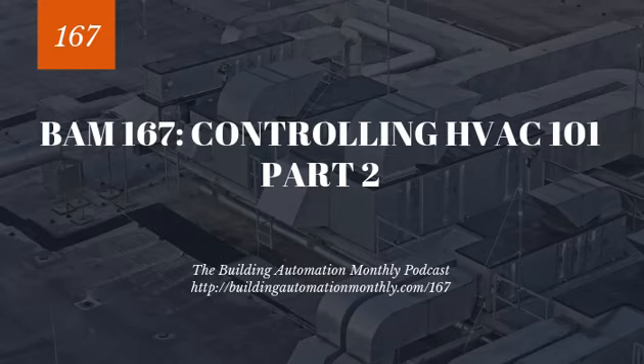Is it going to be manufacturer controls and you're using a BACnet interface, or are you controlling them? Because your ability to sequence systems is going to be dependent on whether you're putting a field controller on, or if you're pulling in BACnet or LON or whatever points from that rooftop unit. So that's the first thing you've got to figure out. Once you know that, let's say you are putting controls on this unit. It's no different. It is kind of different. I'm like, it's no different, but it is kind of different.